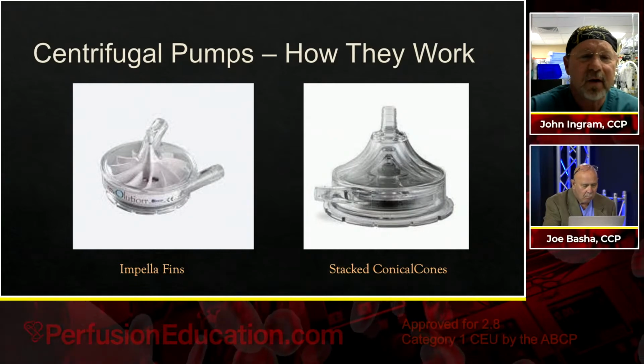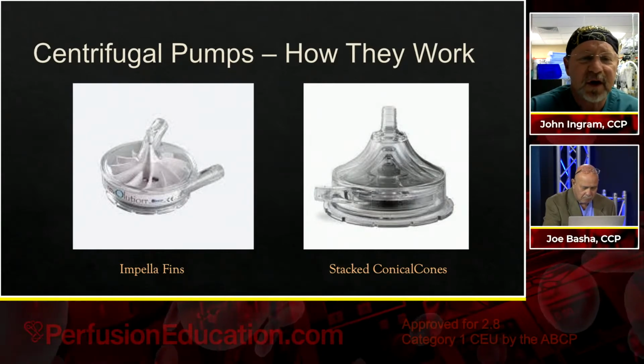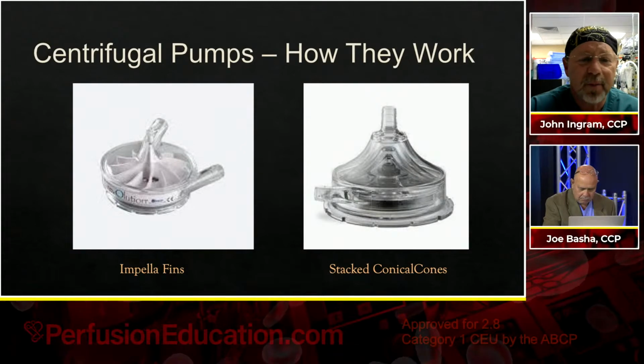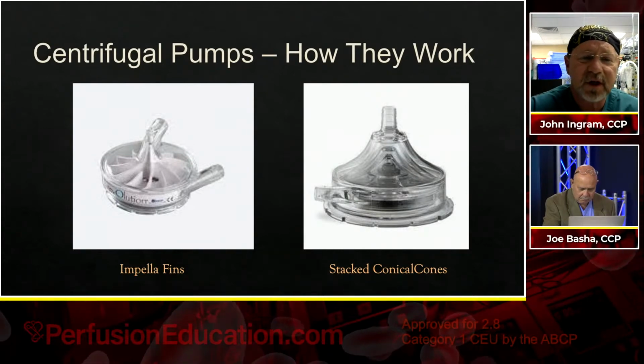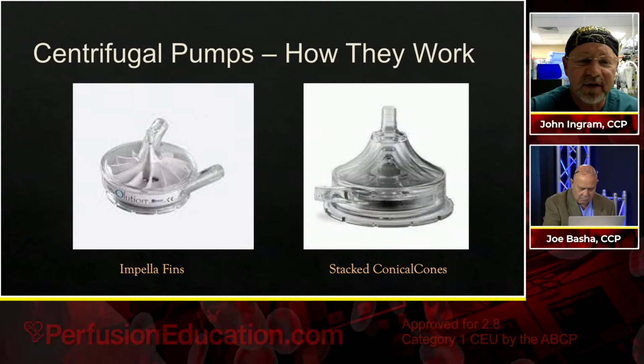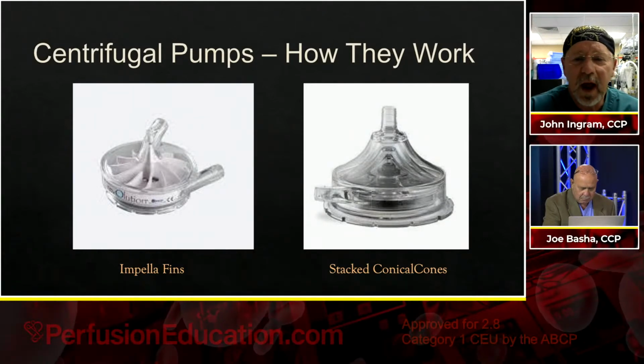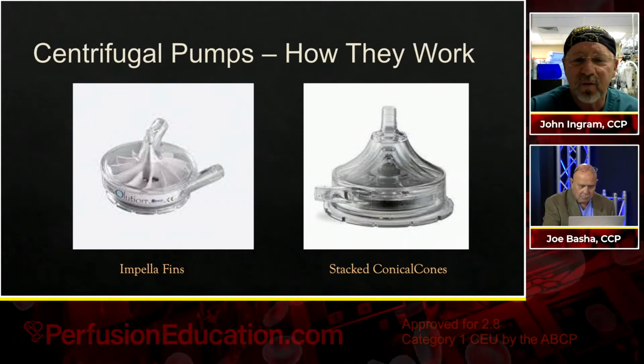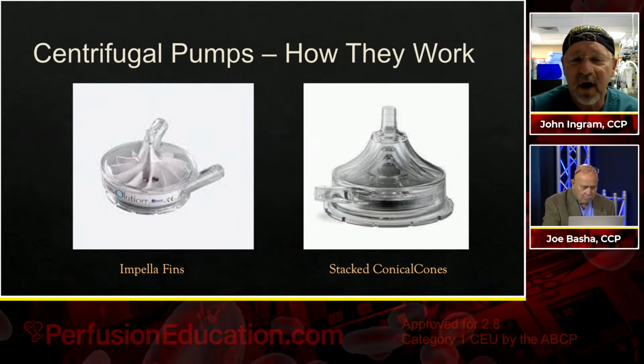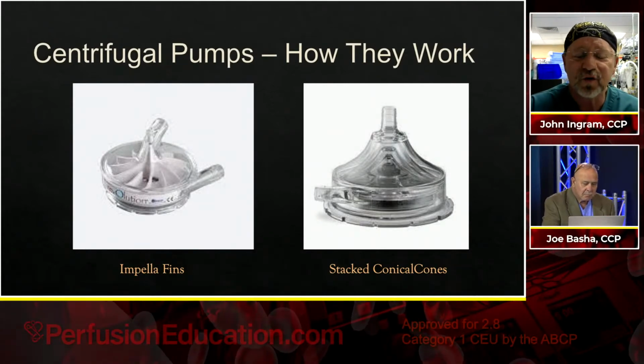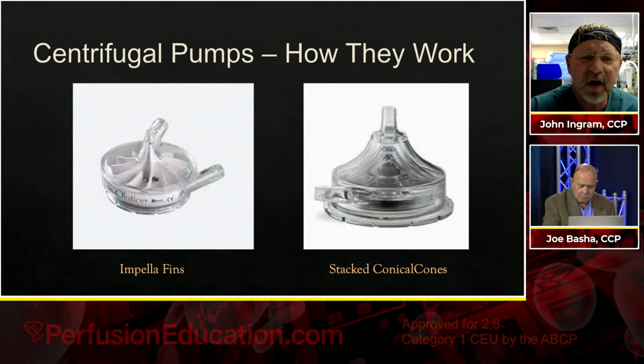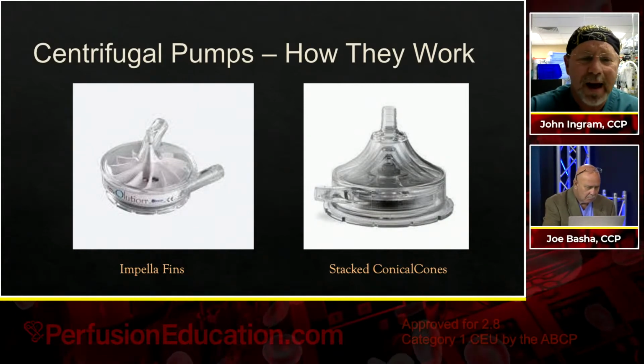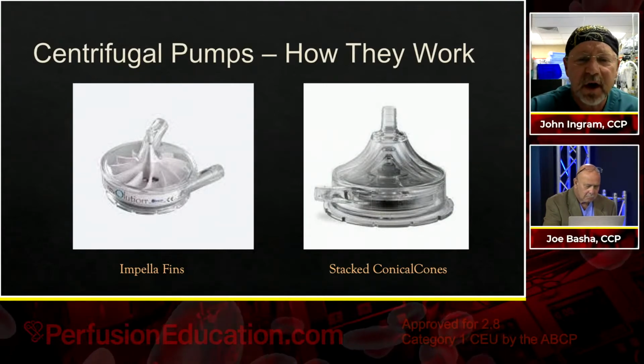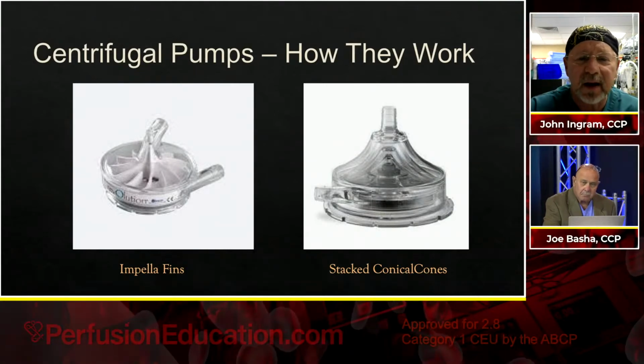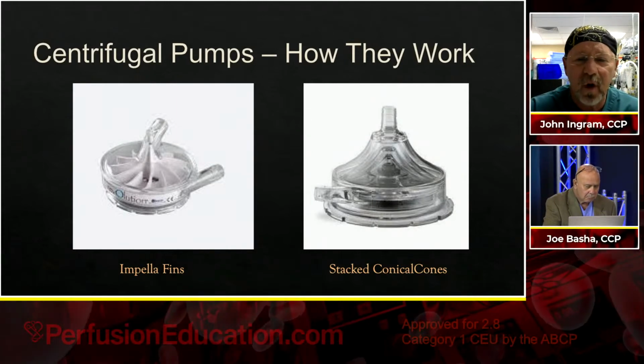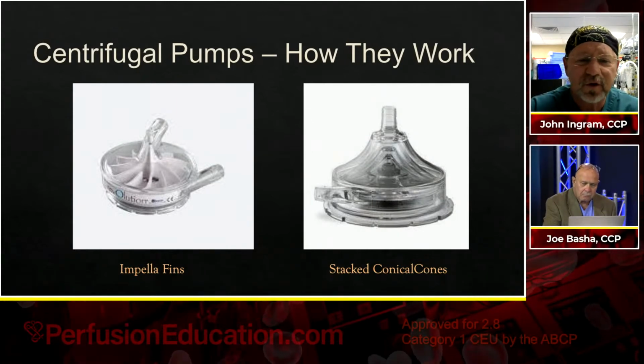So here's a couple diagrams. If you can see the inside mechanism of the pump on the left, this pump is basically using more of an impeller or fins to push the blood forward. And then the other on the right is really a series of stacked conical shaped cones generating a true centrifugal force. The advantage of the one on the left, it would be able to run at a lower RPM because it's physically fan paddling the fluid forward, whereas the one on the right really relies on centrifugal force solely.